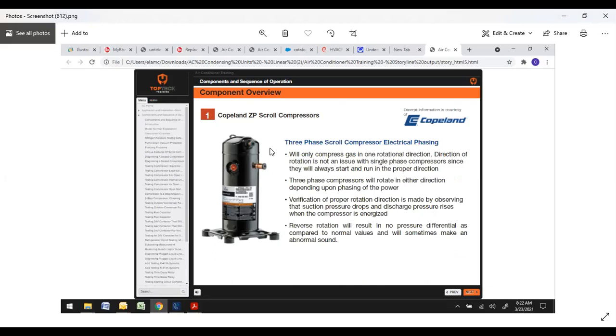Three-phase scroll compressors will only compress gas in one rotational direction. Direction of rotation is not an issue with single phase, since they always start and run in the same direction. You can occasionally get them to run backwards, but you'll know that because of the noise. Three-phase compressors can rotate in either direction depending on phasing of the power.